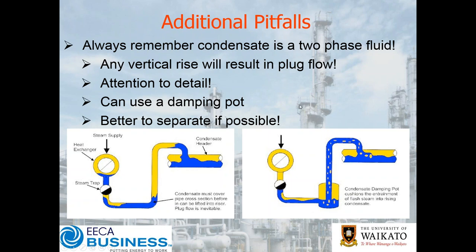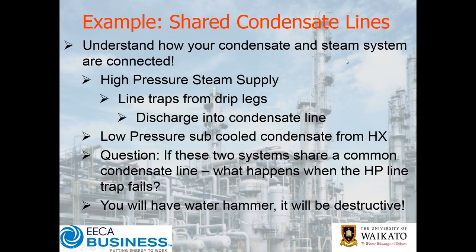The alternative — and actually better — is to actually separate the two and use your flash steam separately if you can. You could potentially put a vent condenser on your condensate tank and use that to preheat some other duty rather than just having it all disappear down your condensate line. There are different solutions — especially if you're talking about traps after a heat exchanger — and having a flash steam section with a flash vessel to separate the two is obviously the best way to go about that.